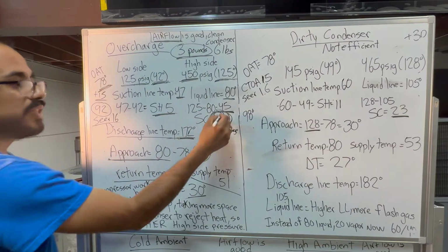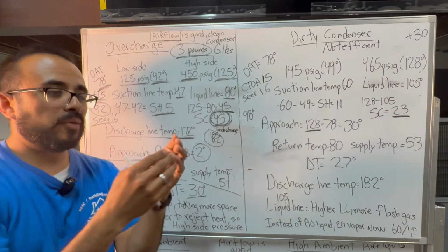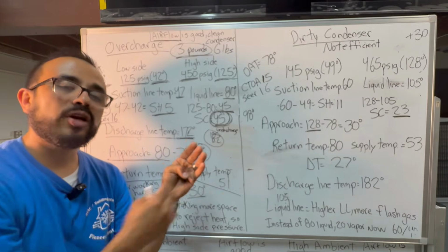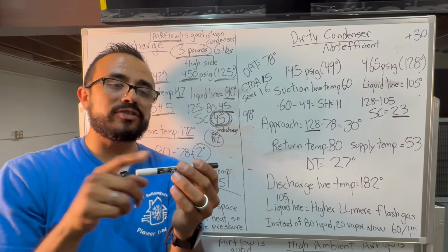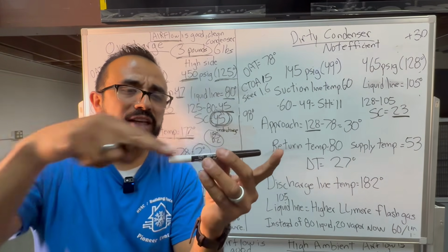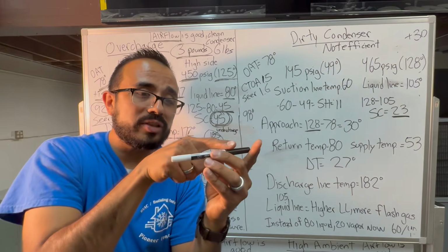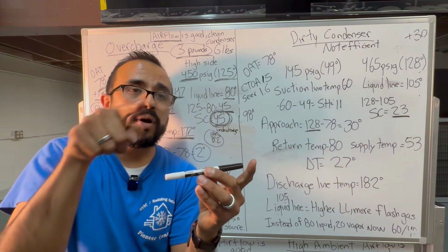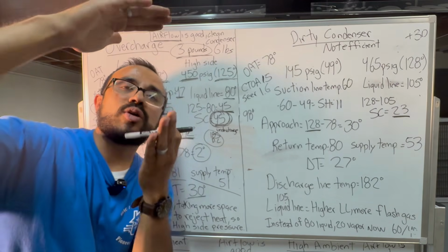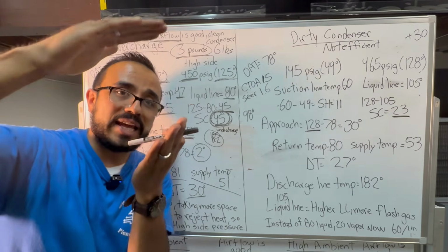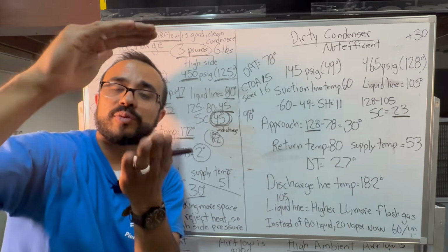And why is it though that my head pressure goes higher? Because think about it. You have a coil, right? We have 45 degrees of subcool. That means that, let's just pretend we have a coil. And when the system's working just fine, 8 to 12, maybe it takes up 2 lines of that condenser coil, just 2 lines. But a subcooling of 45, now it takes up maybe 7 lines of that copper, all that liquid. We filled it up with liquid, but guess what happens? Our condensing coil, now we have less space for that latent heat. We have less space. My pressure is going higher because we have less space to reject heat.